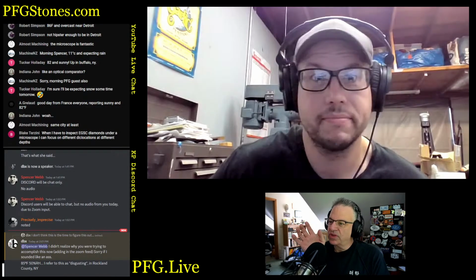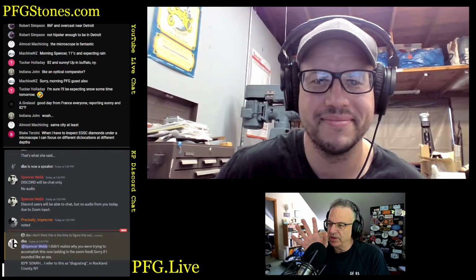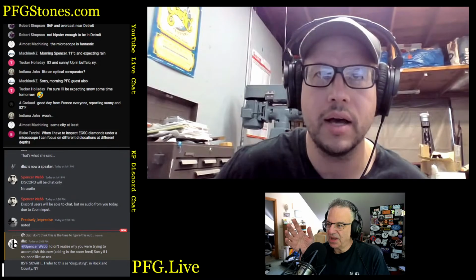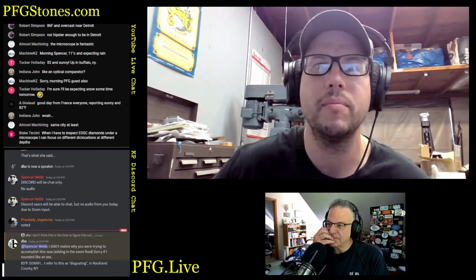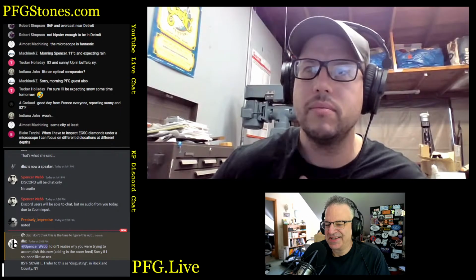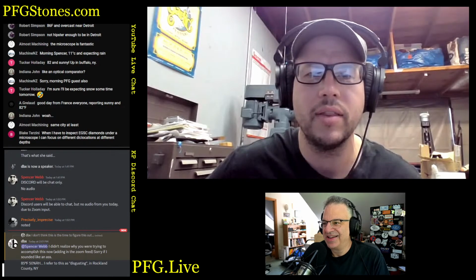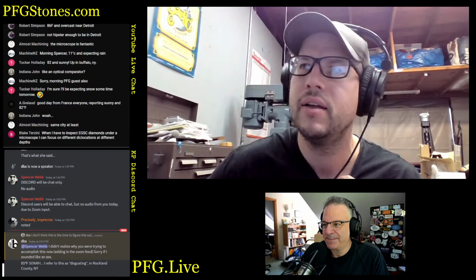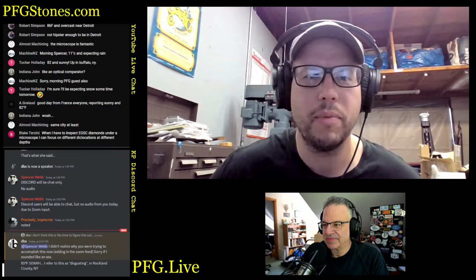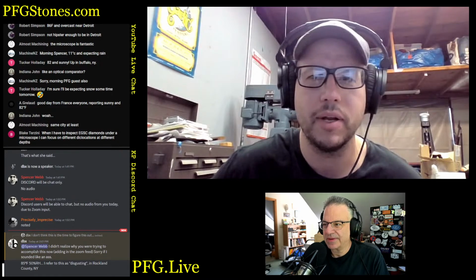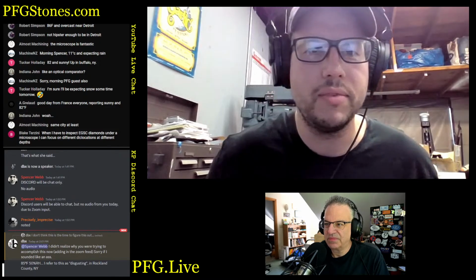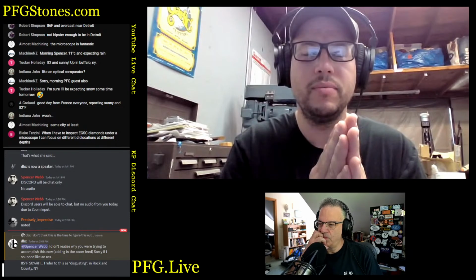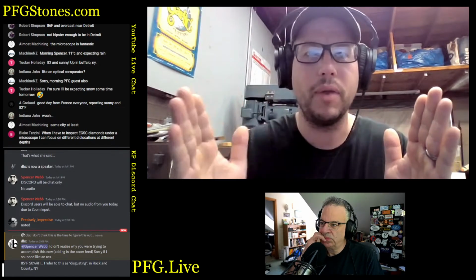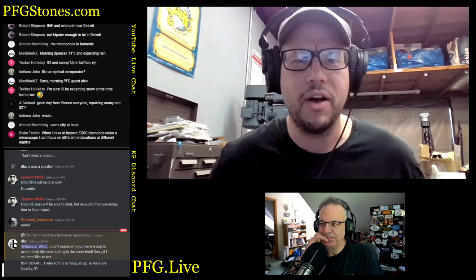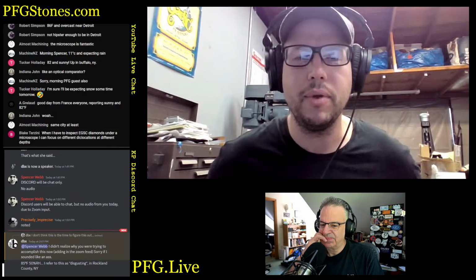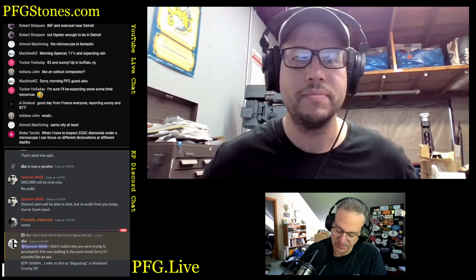Wow. So the standard that they give you is like the Holy Grail. The little glass scale. Yeah. They actually didn't give us one, although I have a couple of, weirdly enough, Zeiss slides that I got from something else. They were using a specially made one, which I think went down to like 5 micron increments, which I didn't even know was possible. I've only ever seen a 10 micron slide, because that's already packed super close. And to use lithography, I'm guessing contact lithography, to get those chromium lines at that spacing with good definition is really, really, really hard. So to do that to 5 microns is kind of mind blowing. But that's what the guy had, and that's what they were using.